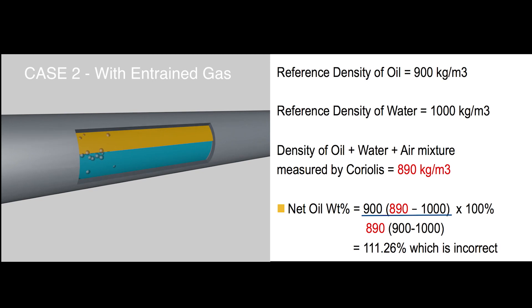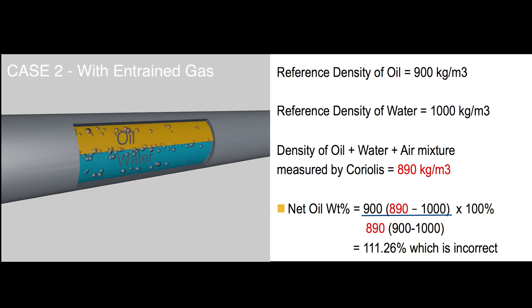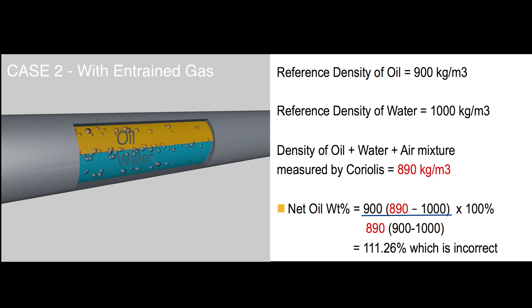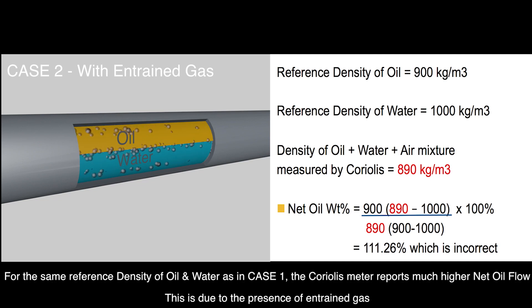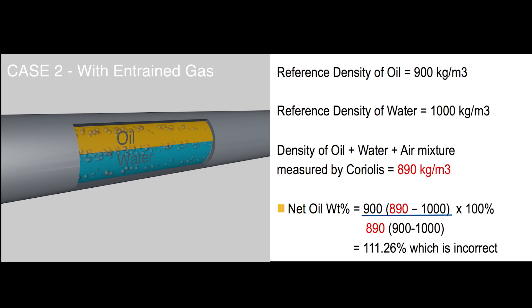Case 2: when entrained gas is present in the oil-water emulsion. The reference density of oil is 900 kg/m³ and the reference density of water is 1000 kg/m³. The density of the oil, water, and air mixture measured by the Coriolis flow meter is 890 kg/m³, because the presence of air causes a density measurement drop. According to the equation, the net oil weight percentage is calculated as 111.26%, which is incorrect.